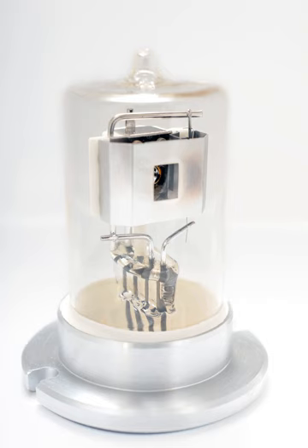However, lamps using deuterium have a longer life span and an emissivity at the far end of their UV range which is 3 to 5 times that of an ordinary hydrogen arc bulb, at the same temperature.